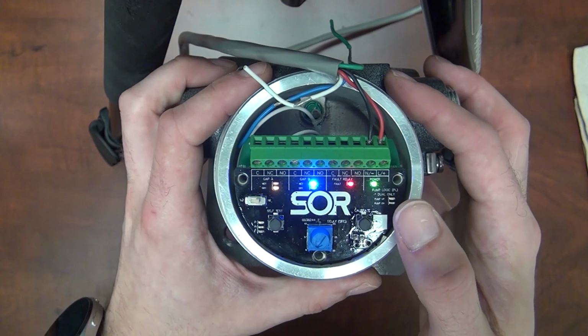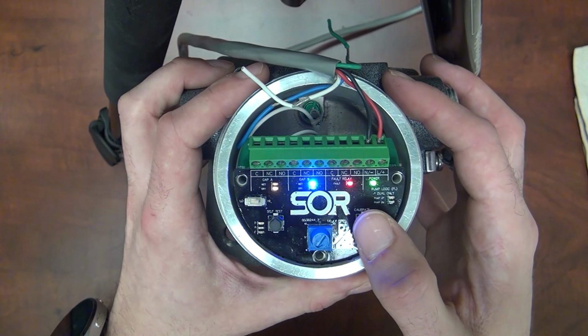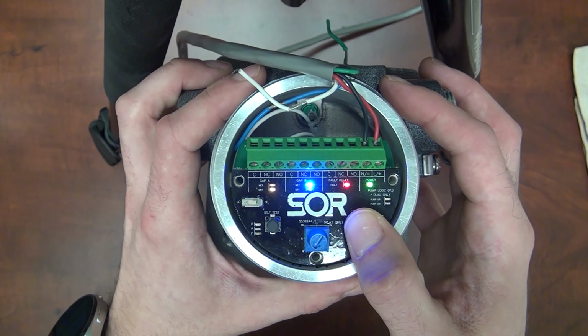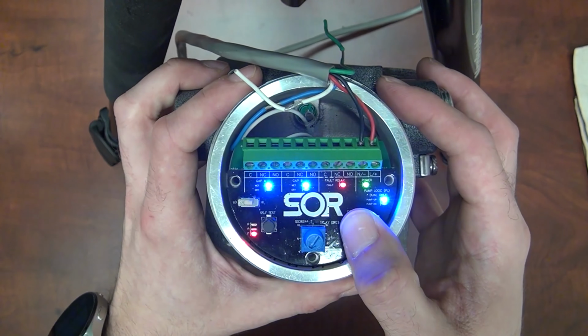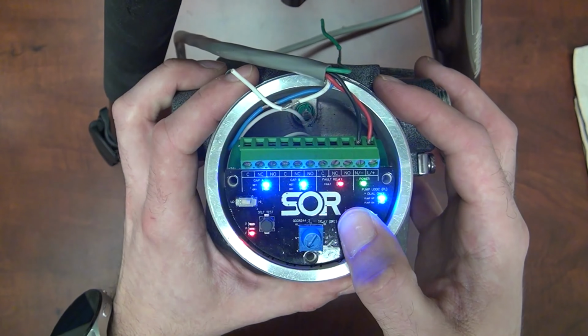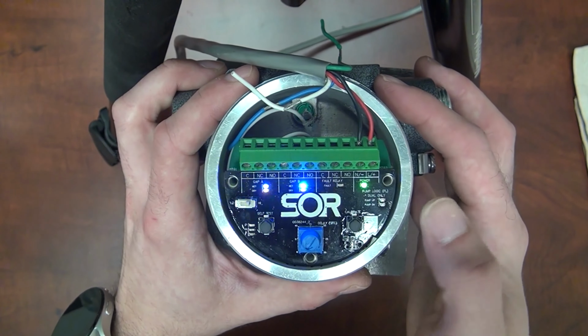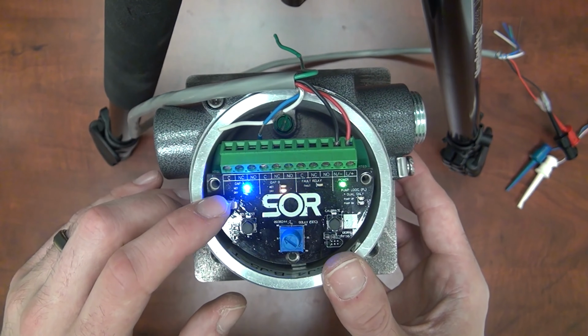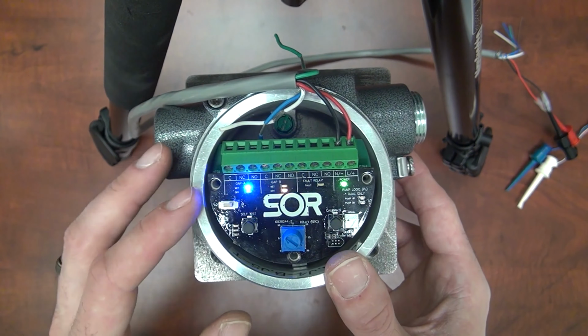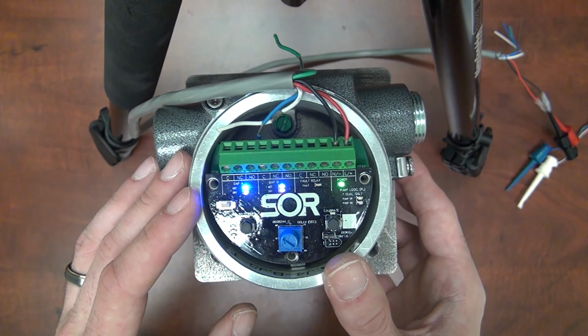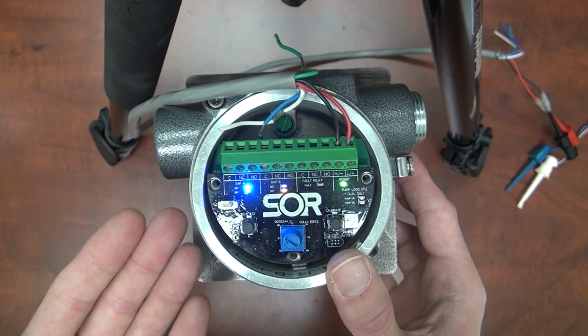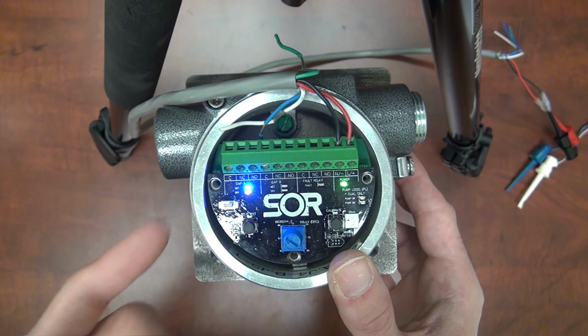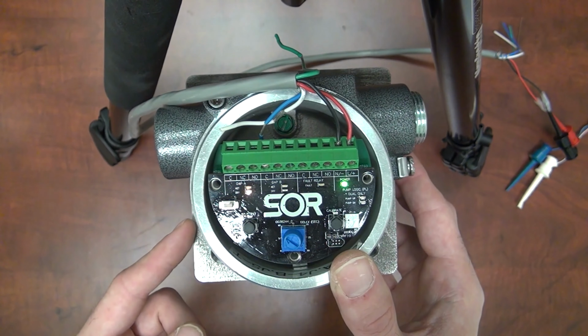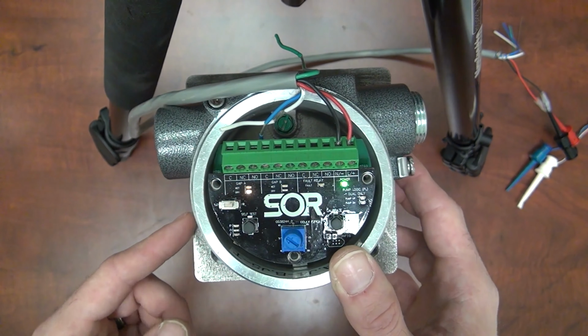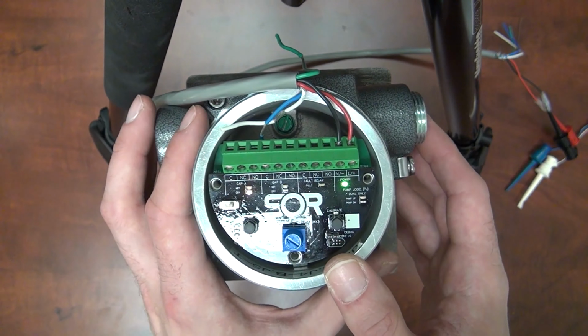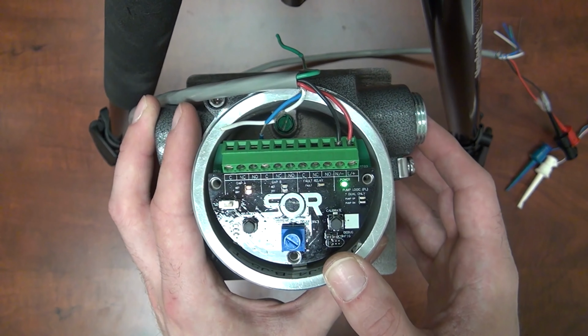Let's start and perform the sensorless calibration procedure. Press and hold the calibrate button for approximately 3 seconds. Afterwards, all the LEDs will begin flashing. When you let go, it is in the calibration selection mode, with the sensorless calibration selected, seen here by these LEDs flashing. Note, after 10 seconds of inactivity, it will leave the calibration state and return, seen here, back to the normal operation. So, once we're in that calibration selection mode, we're going to press and hold calibrate to begin.